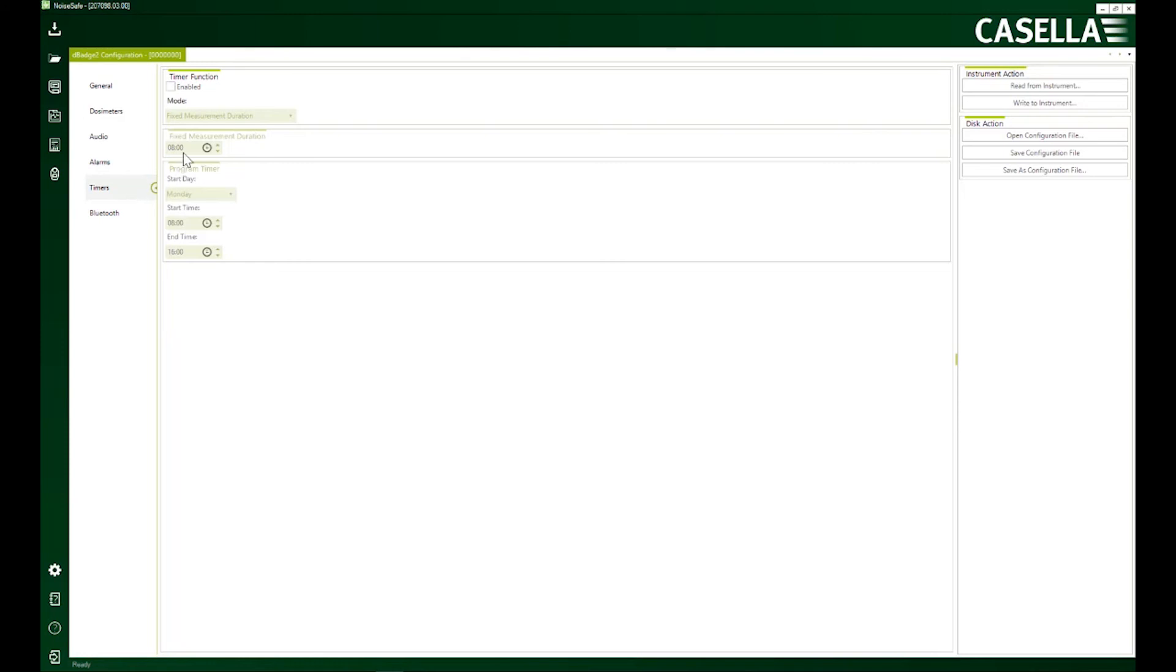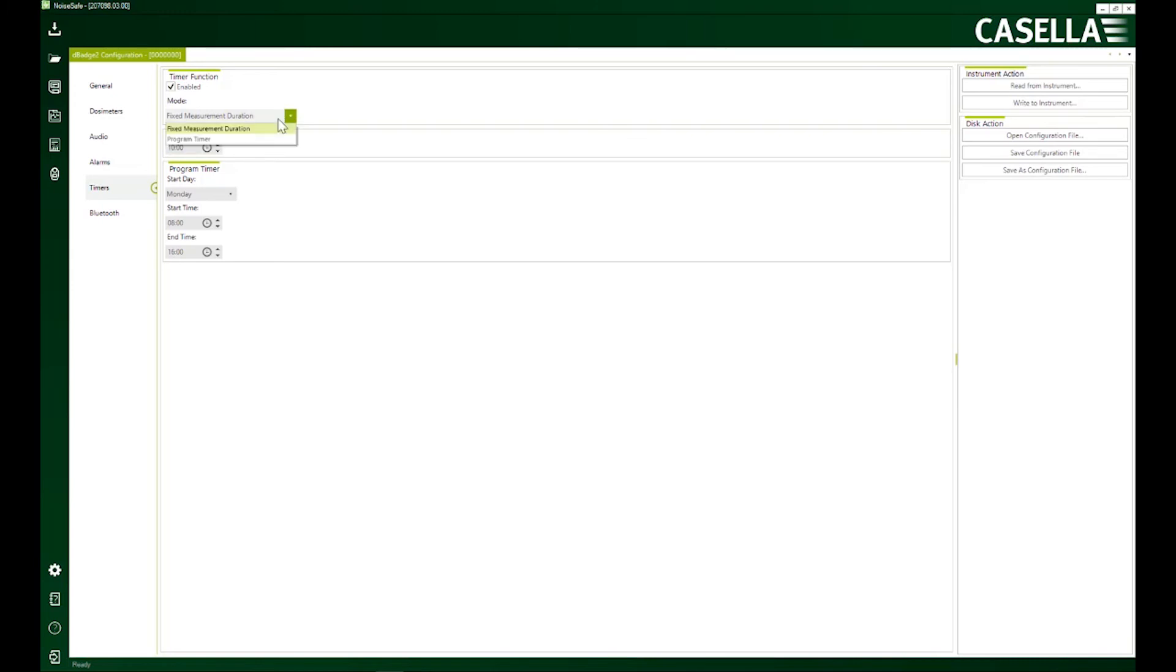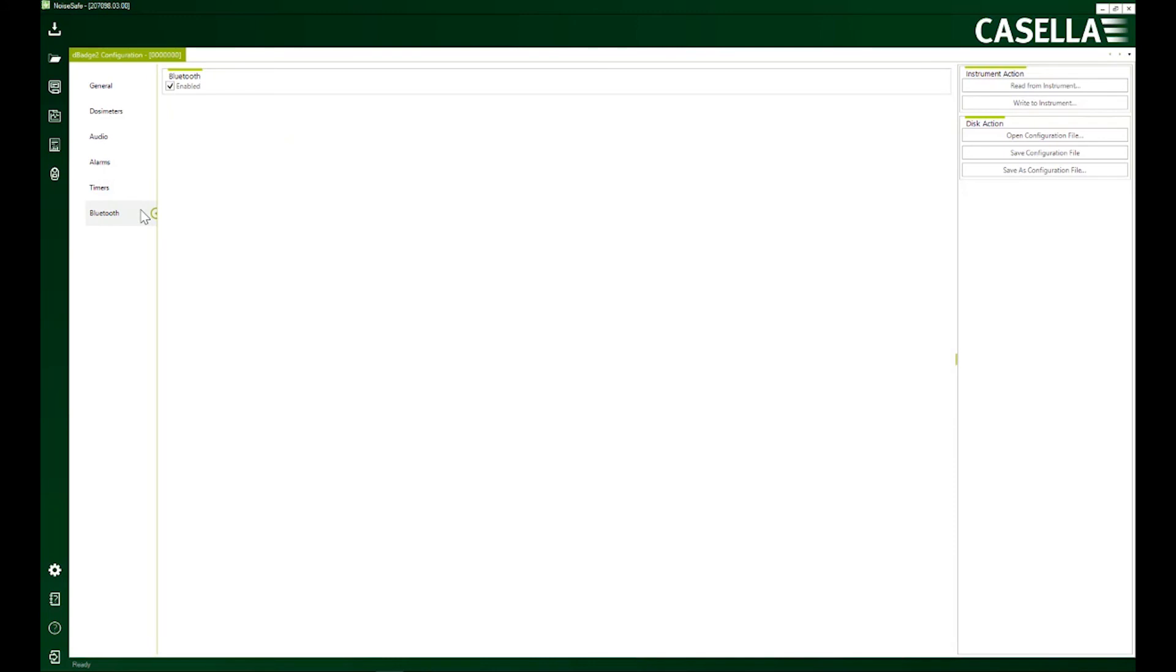Timers. Very important. So you can select the timer function. There are two options available here. Fixed measurement duration. If I select fixed measurement duration and here you can see I've selected number 10. So that means that my measurement durations will be 10 minutes each. And if I select program timer, then I've got an option to start and stop the device at any time and day of my wish.